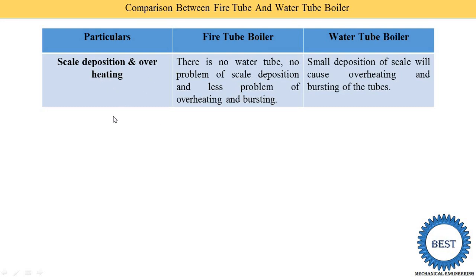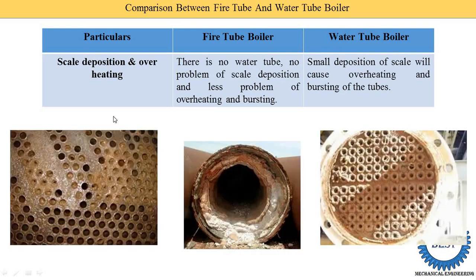Third is on the basis of scale depositions and overheating. What is scale deposition? When anything is used with the water it starts to deposit — that is known as scale deposition. Here I show you some images. This is the boiler and this is the side view of the boiler. When the boiler is a water tube — meaning water is passing inside the tube — a small deposition of scale will cause overheating and rusting of the tubes. Inside the tube this type of scaling is done, and due to the scaling overheating happens and the area for water flow is also reduced. But in a fire tube boiler, water is outside the tube and fire is inside the tube, meaning there is no water inside the tube, so no problem of scale depositions and less problem of overheating and rusting.